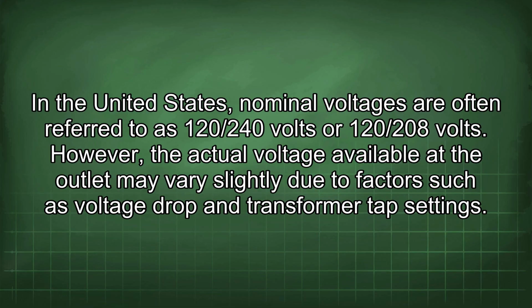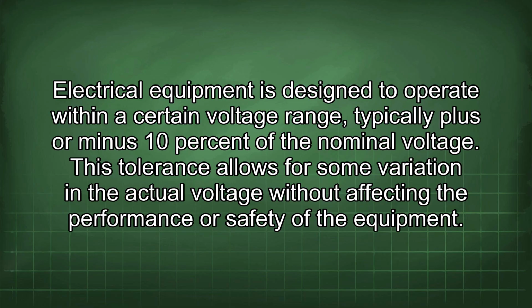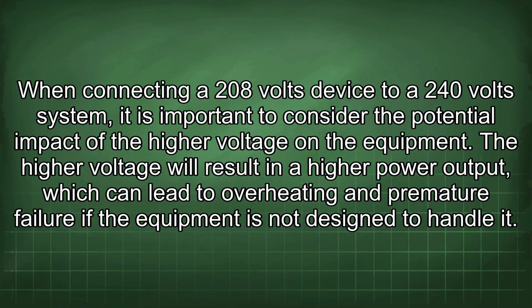However, the actual voltage available at the outlet may vary slightly due to factors such as voltage drop and transformer tap settings. Electrical equipment is designed to operate within a certain voltage range, typically plus or minus 10% of the nominal voltage. This tolerance allows for some variation in the actual voltage without affecting the performance or safety of the equipment. When connecting a 208 volts device to a 240 volt system, it is important to consider the potential impact of the higher voltage on the equipment.